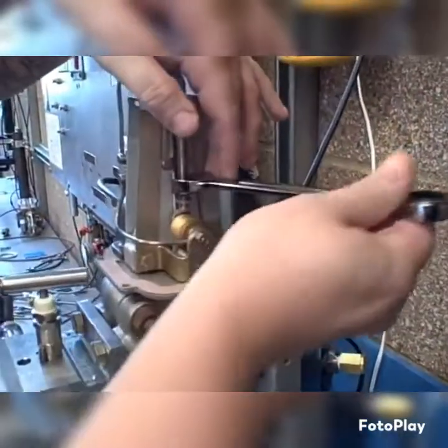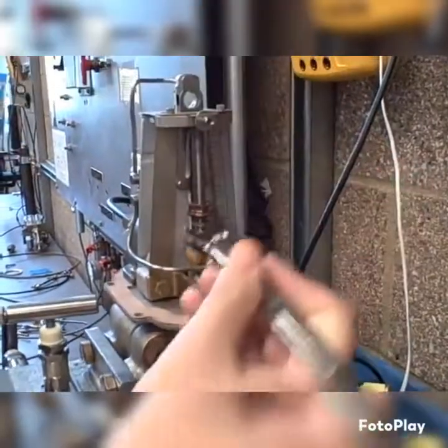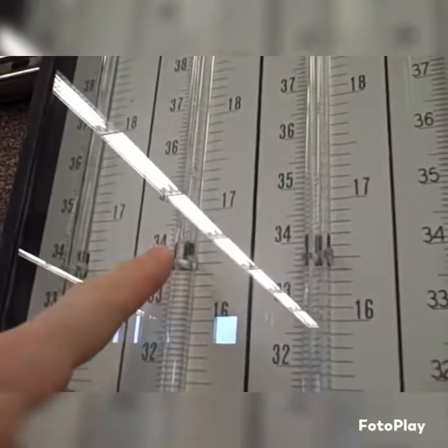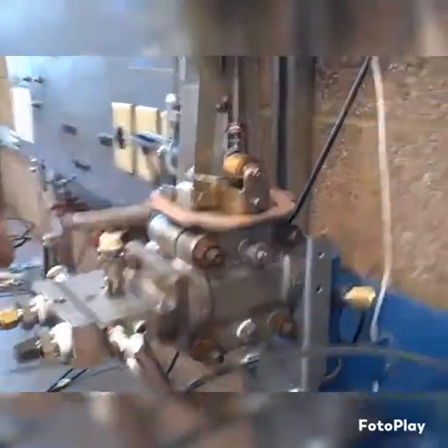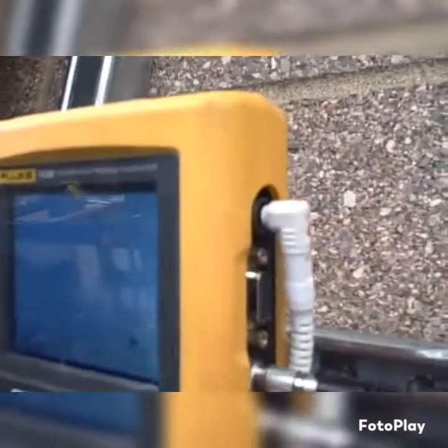Currently you're adjusting the span, the range nut, in the Foxboro model 13A differential pressure transmitter. You have an applied pressure here of 34 inches. 34 inches of water column going to the high side of the differential pressure transmitter, you're shooting for 15 psi on the output.